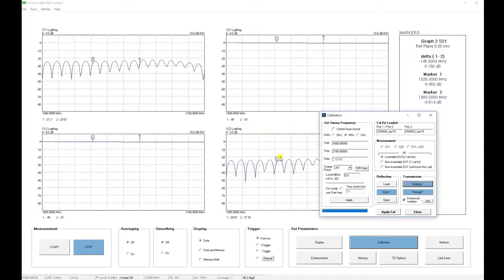The next step is to measure the opens. We make the connections, and click OK. And the final step is the loads. Right, so that's complete, and we now apply the calibration.